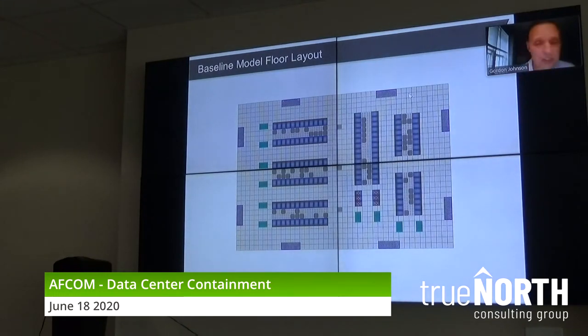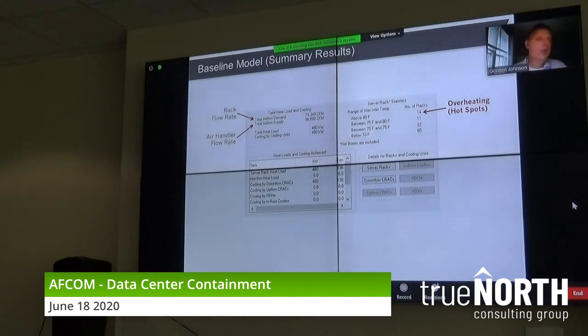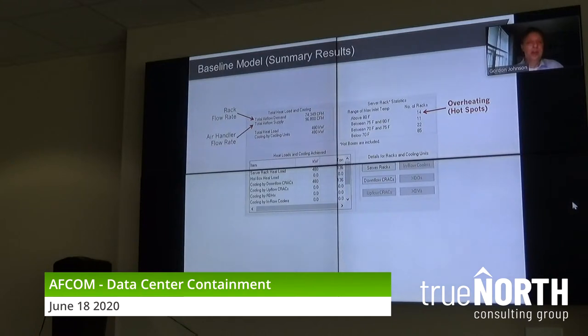Again, natural convection. The hot air exhausts from the back of the racks, goes to the top of the data center, and back into the CRACs. CRAC exhausts, very, very common. This data center initially has a drop ceiling, although we're not using it to start out with. So how is this data center operating with this 62-degree supply air temperature? And also I gave you the supply versus the airflow versus the demand of the IT equipment. This slide kind of gives one quick summary, and then we're going to get into a lot easier way to look at this. Remember the numbers on the left? We said we have 96,000 CFM supply. Our demand, we're estimating it at 74,000. Shoot over to the right, and that red arrow, here's our issue.